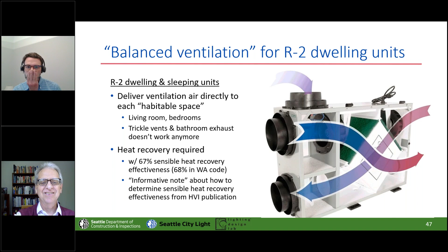DOAS, balanced. So in the last cycle, Duane asked me to critique some of these. You can go with individual little suitcase units like Duane just showed, but you've got to get into every closet and change the filters twice a year. Maybe that's fine if you already have to be in that unit changing filters, maybe not.